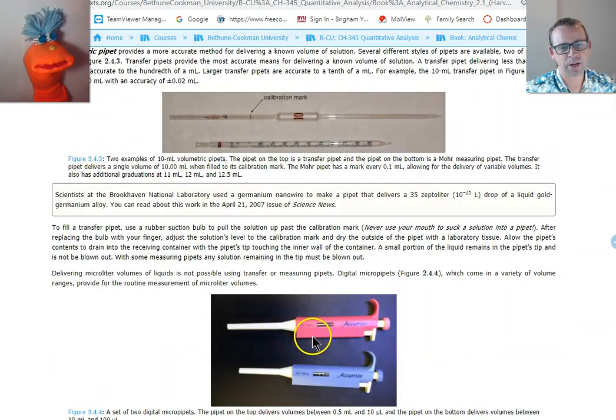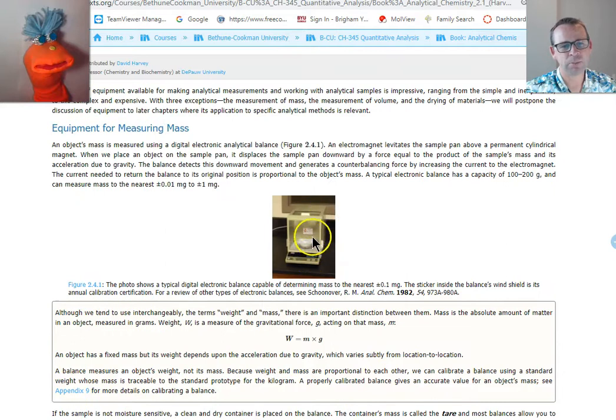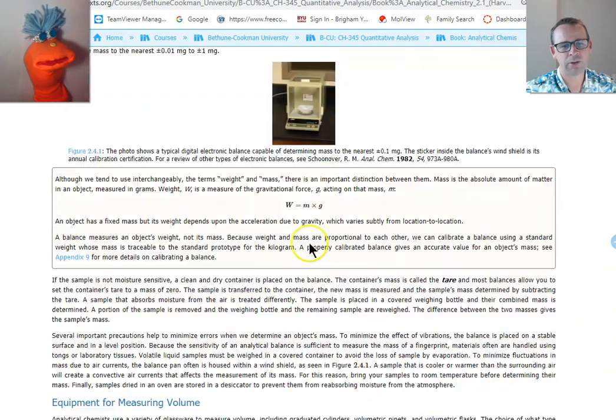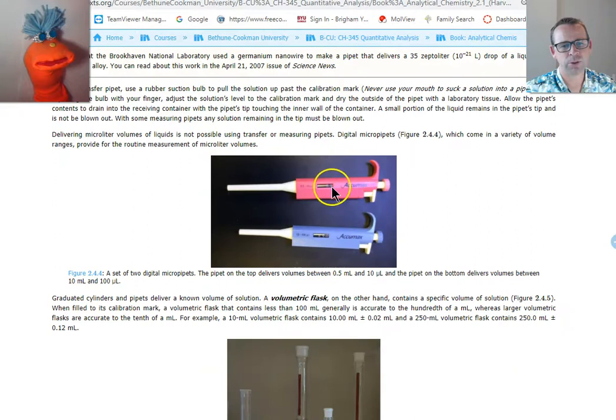So, measuring with the micropipette, you put a bit in some container that's on the balance, and whatever it reads, that is going to be a pretty accurate way of determining that you've delivered your appropriate volume. Now, you don't just want to do that once. You want to do it like 4 or 5 times and take the average, because there's a lot of manual error, user error, that can occur. Okay?